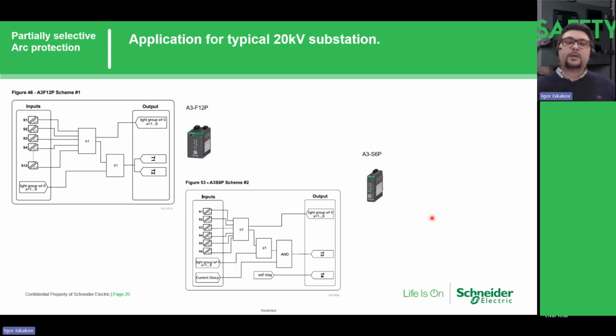This is also a very cost-efficient solution for some old switchgears, and easy to implement and take into use. You don't need a configuration tool. You don't need a PC. You just choose your scheme, which could be predefined, and after that choose the light groups and scheme on the DIP switches on the device. Using the push button, you can configure the whole system.